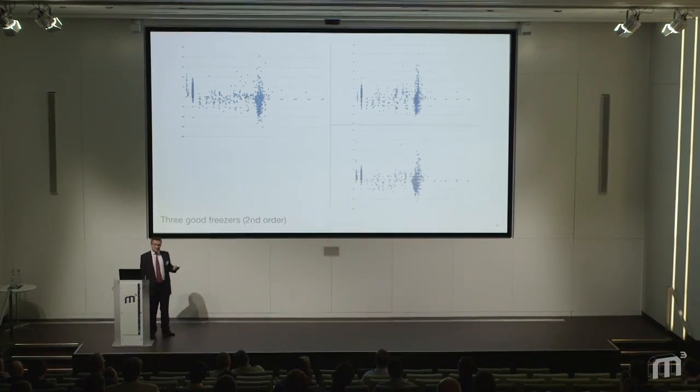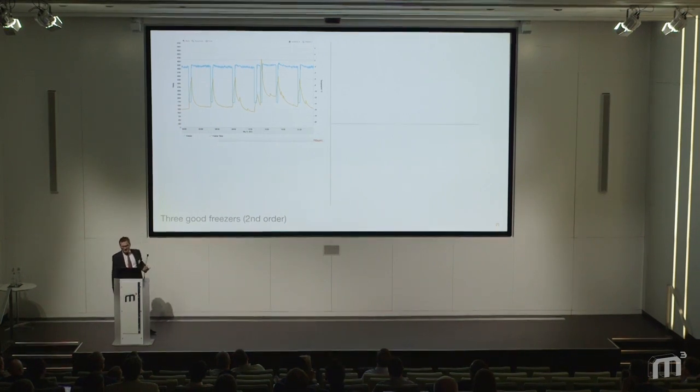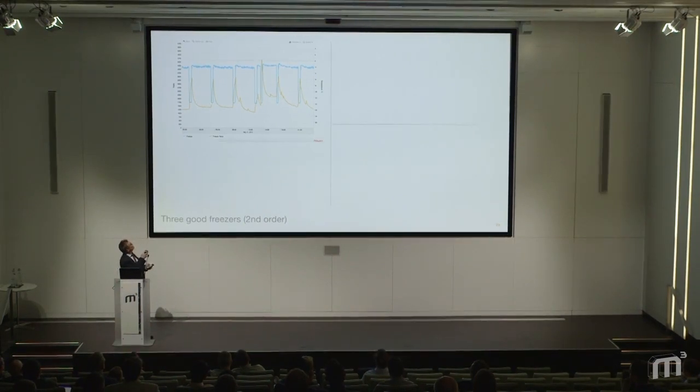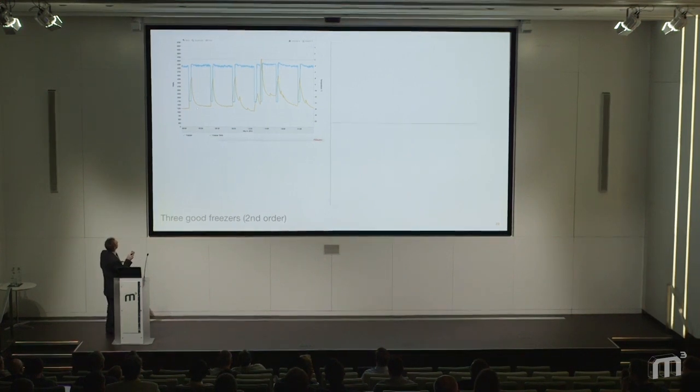Let me show you a freezer that will fail in the next few months. Here, the blue line of the compressor is running almost constantly. Yeah? The temperature is going down very slowly. This is indicative of a gas leak. There's something wrong with this device. But of course, the user would never know this because what he'd do is he'd probe the food in the morning and set points being reached, you see. So he wouldn't know anything's wrong.